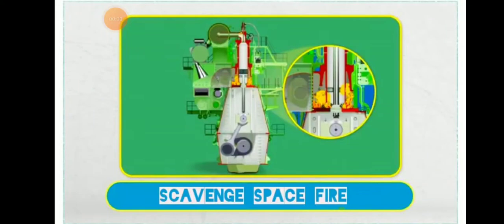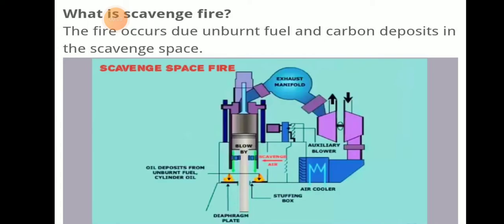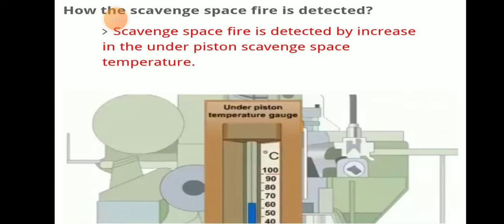Today we will be discussing scavenge space fire — what are the indications and what actions need to be taken. Scavenge fire is a fire that occurs due to unburnt fuel and carbon deposits in the scavenge space. Oil deposits from unburnt fuel and carbon deposits accumulate there, and when fire occurs due to this, it is known as scavenge fire.